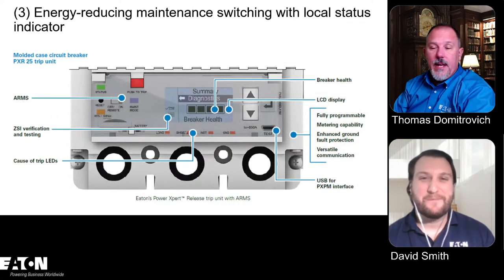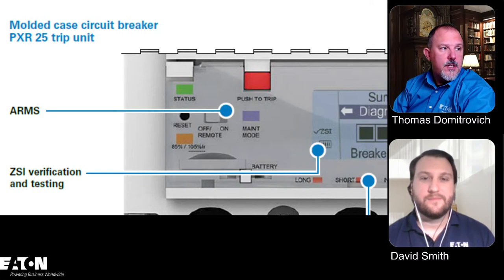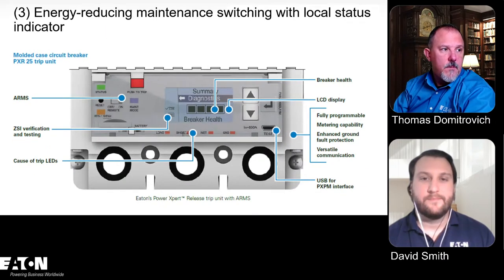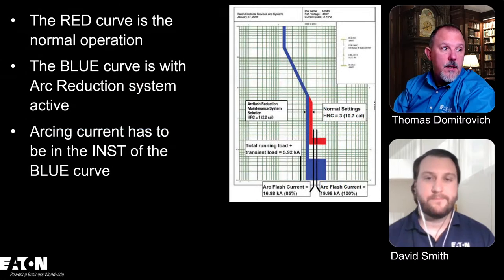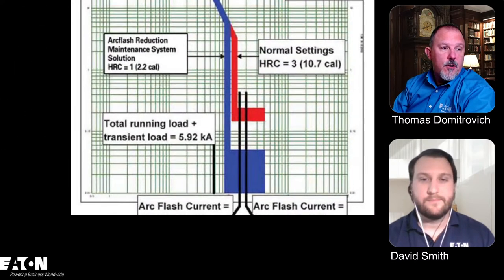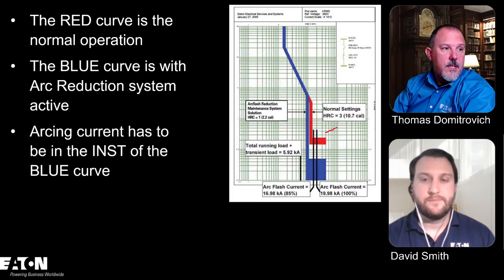And this is what we would have on a molded case circuit breaker. So there's your switch right in here, and that's on and off. Then you can establish the performance of that in the settings. And this is basically what it's doing. You're taking your trip curve, your delay. This red curve is basically how that device would have operated without the arc reduction maintenance switch, and the blue is how it acts with it.